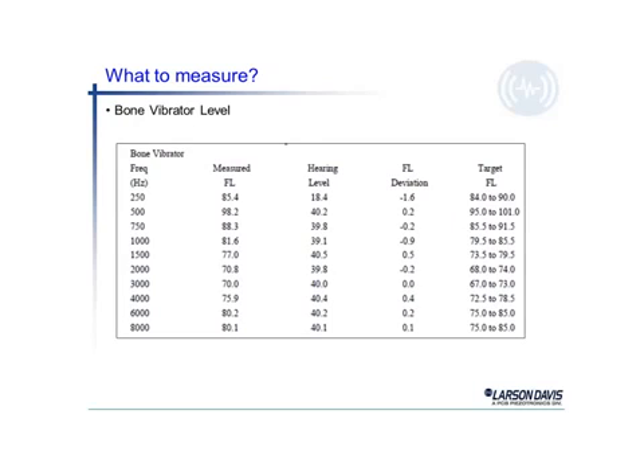We can also measure the bone vibrator level, as we talked, that little artificial vibrator. Again, if we use the example at 1000 hertz, we see a measured FL, or force level, of 81.6. That equates to an actual hearing level in vibration terms of 40 dB would be the ideal. This one measured 39.1, giving us a deviation of 0.9, and again well within a target level that we'd like to see, the force level somewhere between 79 and 85.